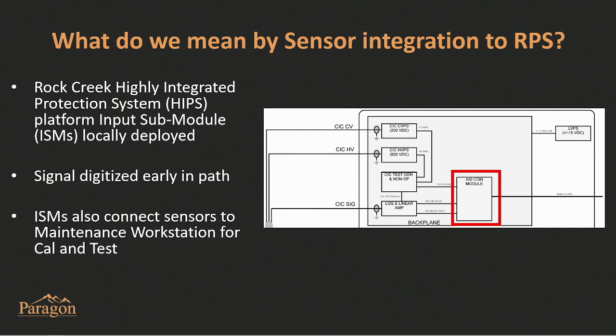It is a source of noise and other issues. We actually took the reactor protection system field module, the input submodule, from where it would normally be in the control room and moved it all the way out into the containment area so it would be locally deployed. That allowed us to digitize that neutron flux monitoring system early in the signal path, which has a lot of benefits I'm getting ready to go through. But most importantly, it extends the reactor protection system boundary all the way out, so it's covered by the same licensing basis and the same common cause failure analyses. So it works very well in that environment.